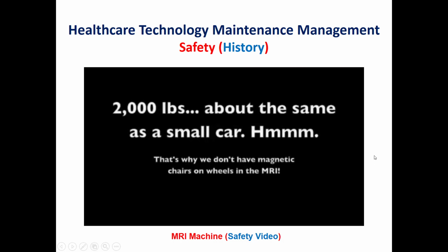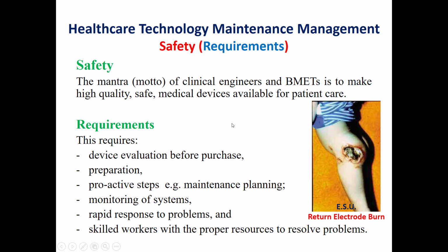So the attraction force of a 4 Tesla magnet in an MRI machine had reached 1800 pounds. Imagine what this force could cause for a patient or any type of equipment.